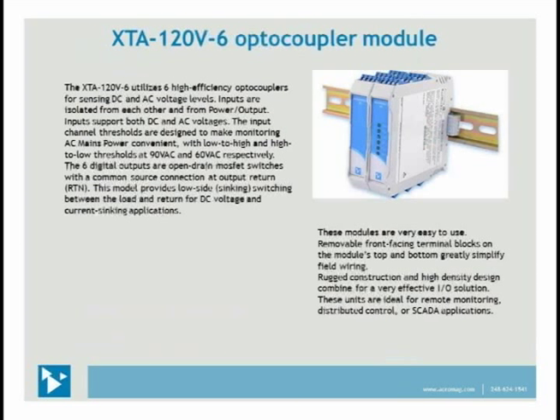Now I'd like to talk a few minutes about the XTA-120V-6 optocoupler input module. The XTA-120V-6 utilizes 6 high-efficiency optocouplers for sensing DC and AC levels on the input. The inputs are isolated from each other and from the power supply and outputs. Inputs support both DC and AC voltages. The input channel thresholds are designed to make monitoring AC mains power convenient, with low to high and high to low thresholds at 90 volts and 60 volts AC, respectively.